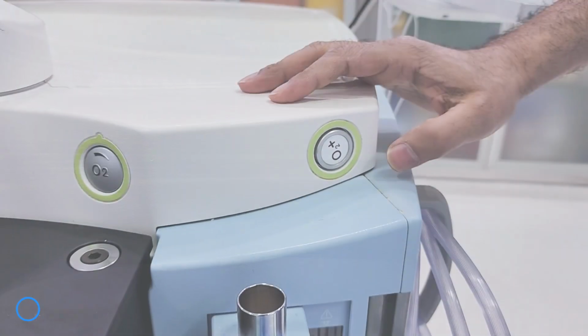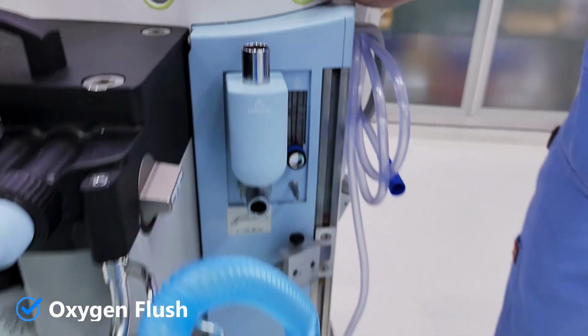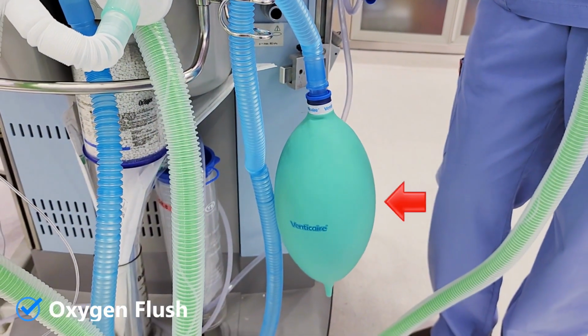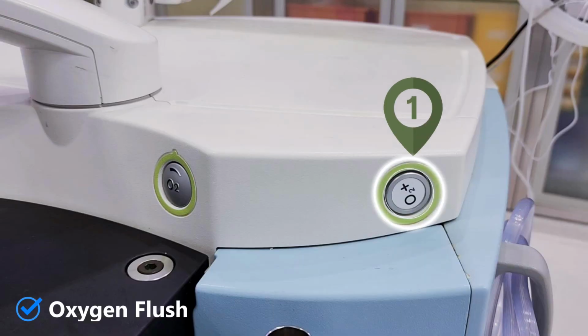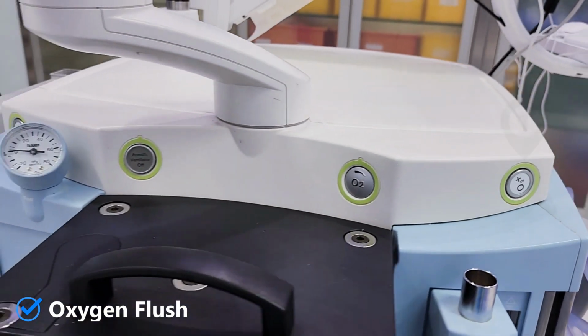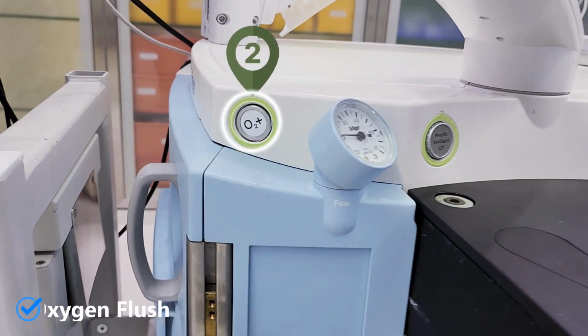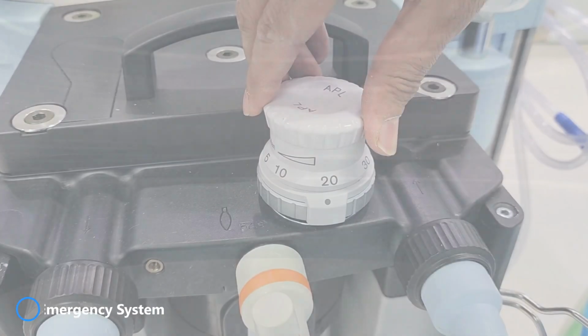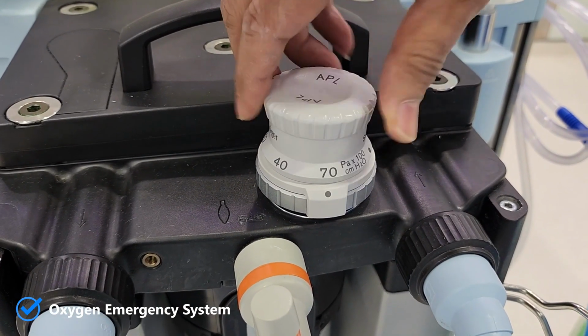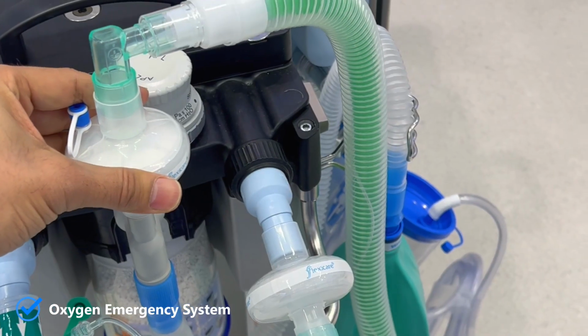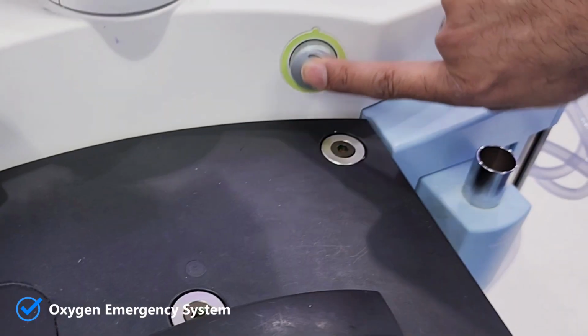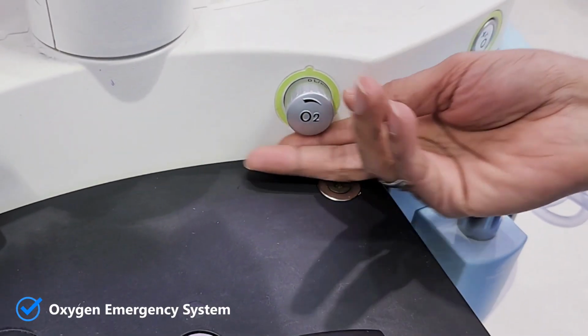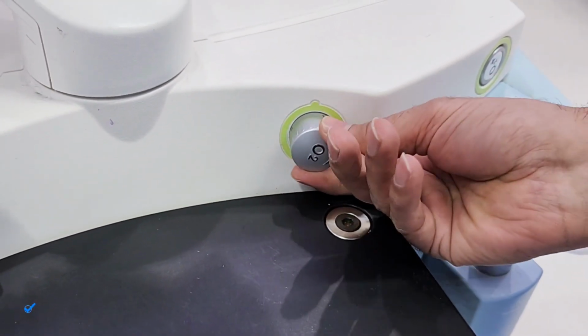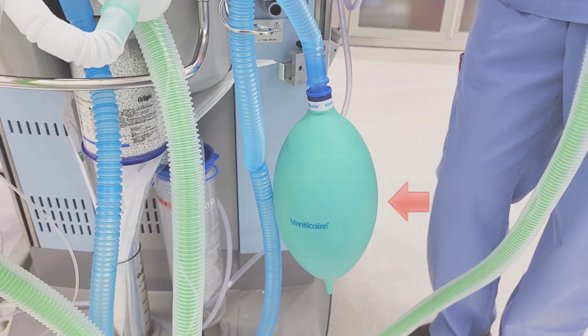To check the oxygen flush button, activate the oxygen flush valve and see that the reservoir bag is getting filled. Zeus machine has 2 oxygen flush buttons. To check the oxygen emergency delivery system, close the APL valve. Occlude the breathing circuit. Activate the oxygen emergency delivery system. And see that the reservoir bag is getting filled.